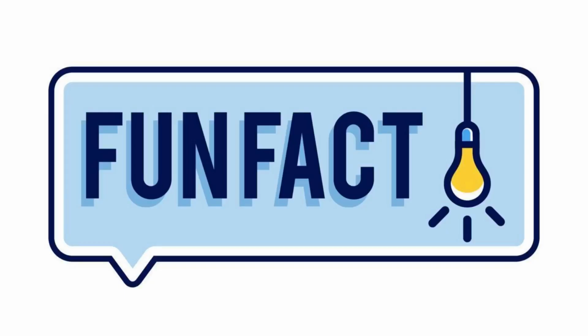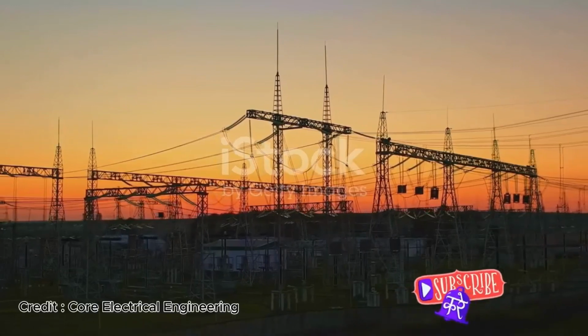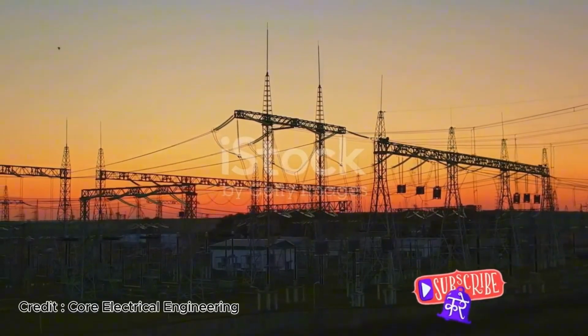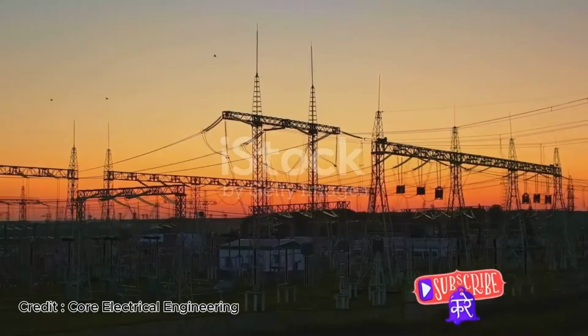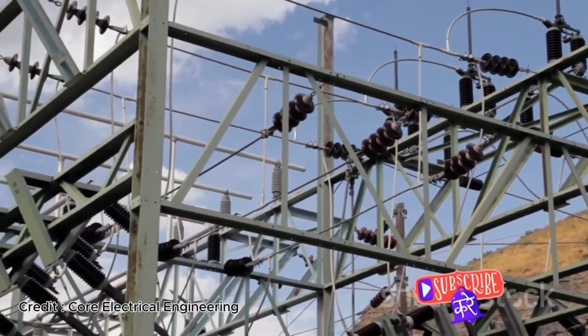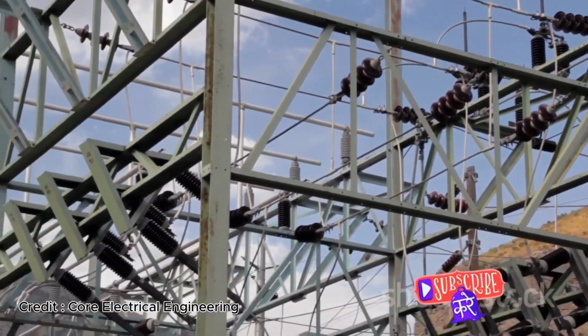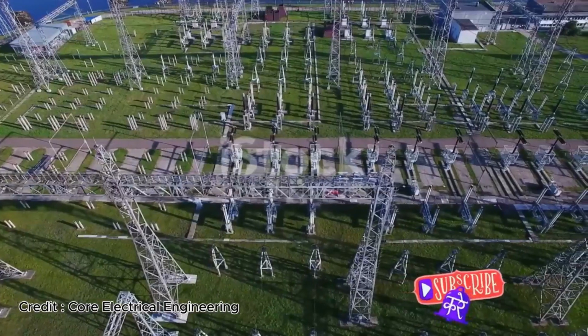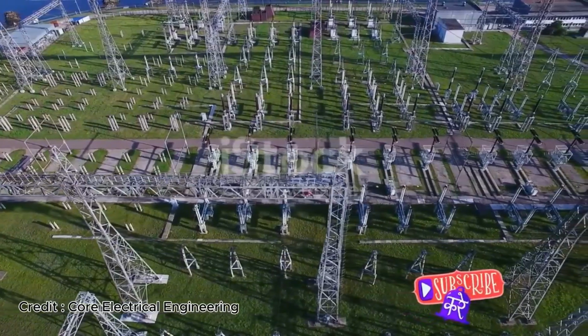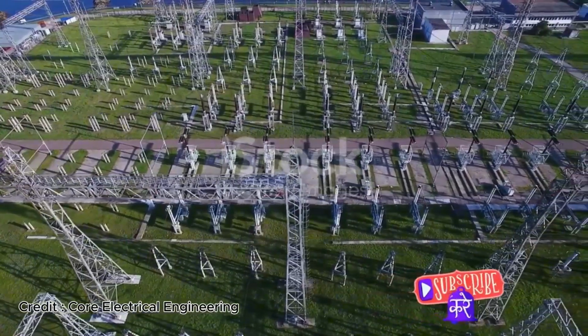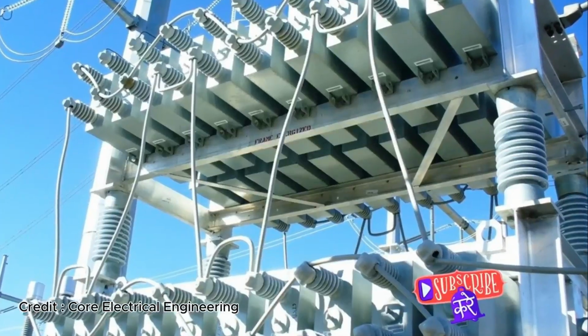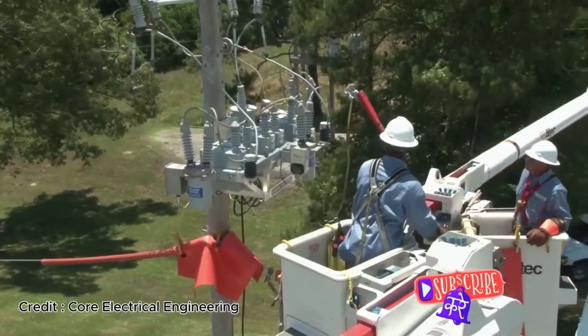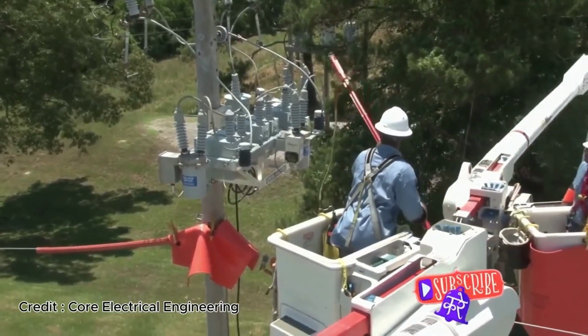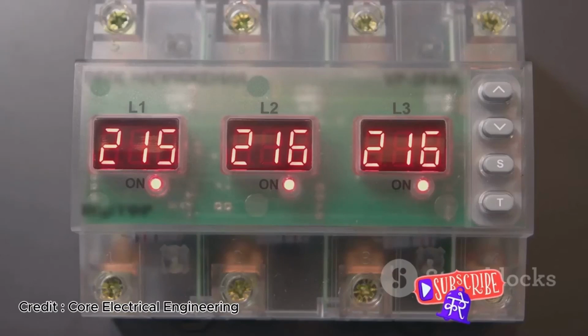It's fun facts time. Did you know that capacitors play a main role in electrical distribution? Capacitors help power systems work more efficiently and maintain the quality of power supply. Firstly, they help in power factor correction. Most loads like motors are inductive and cause the current to lag behind the voltage. This creates reactive power, which does not do useful work but still loads the system. Capacitors supply leading reactive power, which cancels out the lagging reactive power from inductive loads.